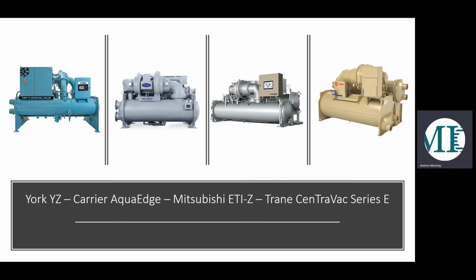To put that in a little context, here are the machines that are using that ZD refrigerant, which is the ASHRAE highest rated class, A1. It has a global warming potential of 1, and with the nature of low pressure, it is the most environmentally friendly and efficient chiller on the market. So we have the York YZ, Carrier Aqua Edge, the Mitsubishi ETI-Z, and the Trane CenTraVac Series E.